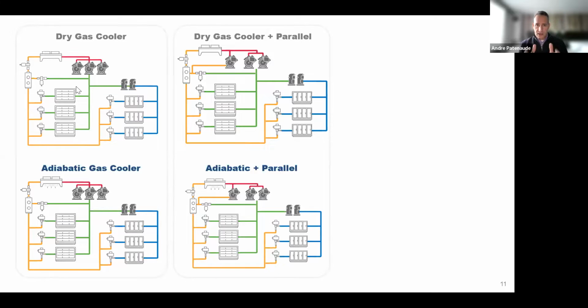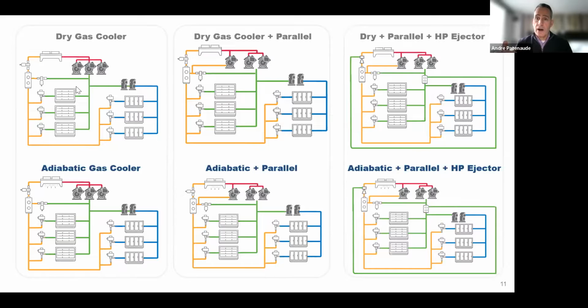And then we wanted to look at, well, take that same architecture with an intermediate or parallel compressor and add adiabatic. And the next step, we wanted to layer in now dry gas cooler, parallel compressor, and then you can see above the flash tank in the top right image, there's a little image there of a gas ejector. And you can see the side port goes all the way to an accumulator at the inlet of the medium temp compressor. So your medium temp cases' vapor is going into that accumulator, your low temp discharge going into that accumulator. Now we're siphoning vapor off of that accumulator so that my medium temp compressors don't have to work as much. We want to send that to a parallel compressor. So there's an energy advantage adder to that because we're pushing more vapor to my parallel compressor for longer periods of time. So that's important to look at. And then the bottom one, we add adiabatic. So those are the main 6 buckets, if you will.